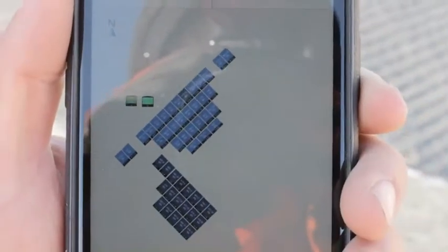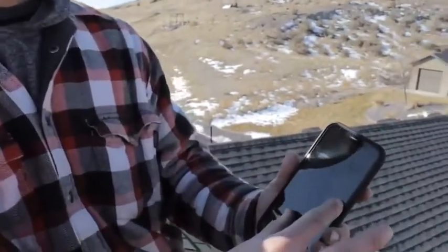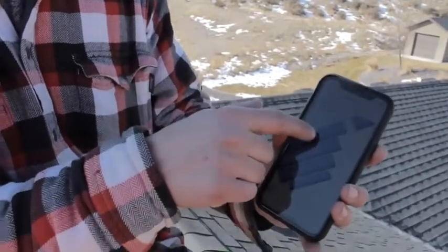There's an app where we can actually see how much power each of the individual panels are producing. We can go ahead and take a look at this system, look at the panel, and very easily find that this one right here is producing way less power than all the panels around it, so we know that there's an issue.